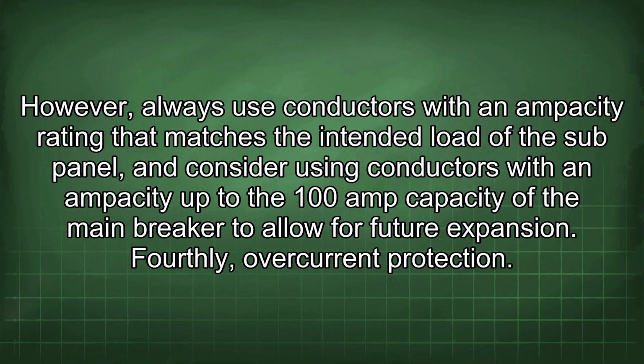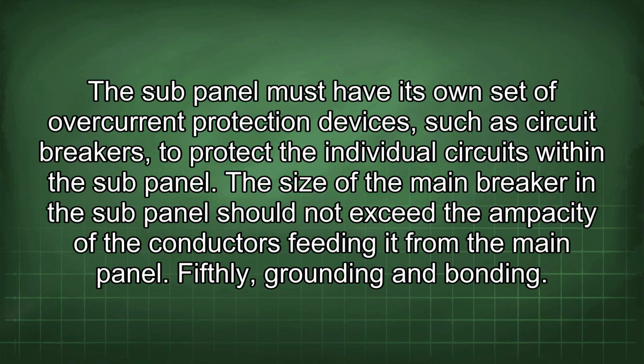Fourthly, overcurrent protection. The sub-panel must have its own set of overcurrent protection devices, such as circuit breakers, to protect the individual circuits within the sub-panel. The size of the main breaker in the sub-panel should not exceed the ampacity of the conductors feeding it from the main panel. Fifthly, grounding and bonding.